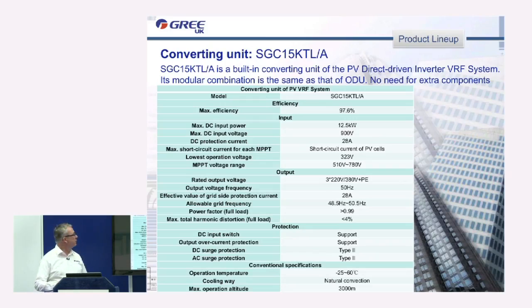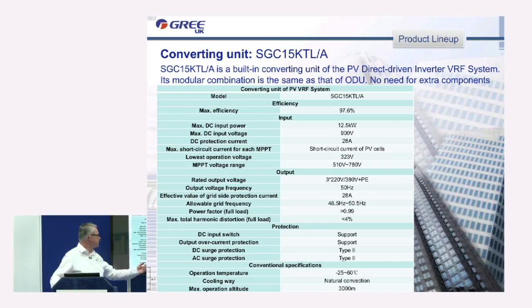The actual component within the outdoor unit, which controls and manages the power flow, is a printed circuit board type unit with other components such as reactors, as I mentioned, and the film capacitors, and it's all controlled electronically within the unit itself, and that's a specification of the unit. And one thing you'll notice is that the power factor is 0.99 within this control box. So it's not having any detrimental effect on any external power supply. It's rated very highly. The harmonics are less than 4%. So again, we're not causing any problems with interference. We're not getting any interference into it. So it's a very safe system. It can work up to an operation temperature of 60 degrees C and down to minus 25. So again, conditions within the UK mean it's a very usable piece of kit.